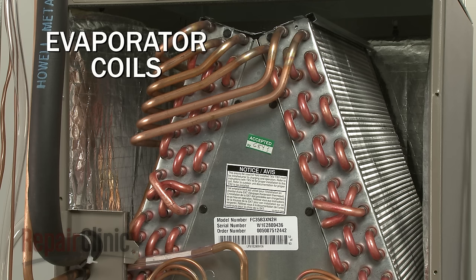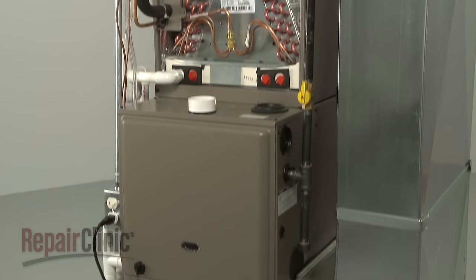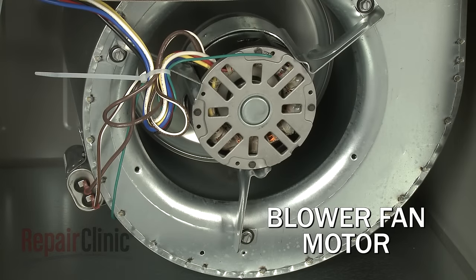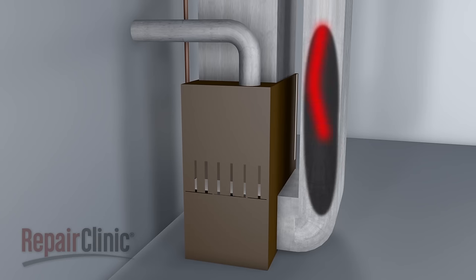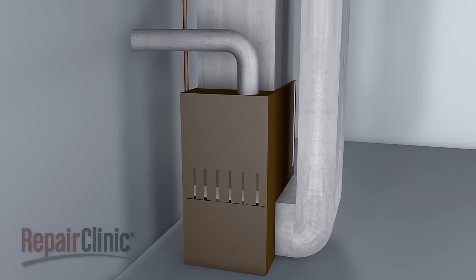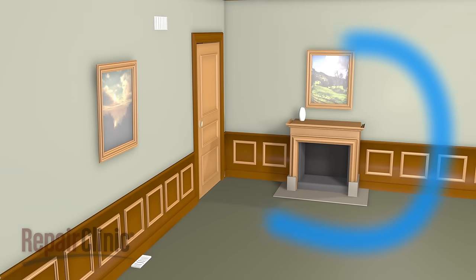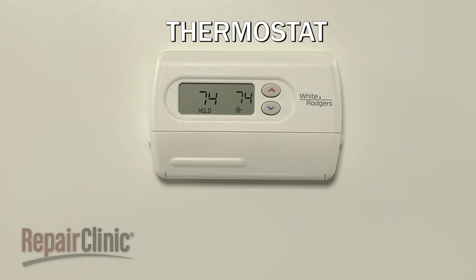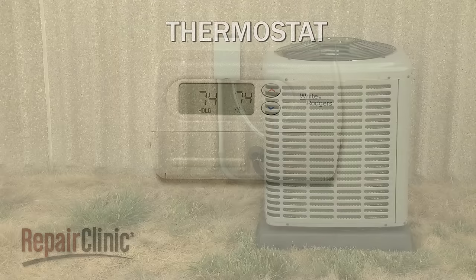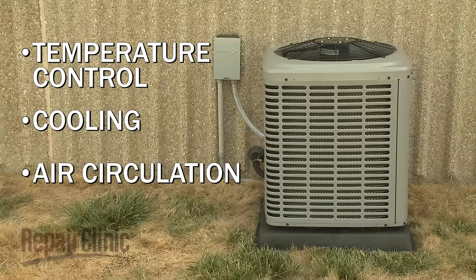The evaporator coils, or cooling coils, are located inside the home and are mounted on top of a furnace or air handler. The furnace or air handler uses a circulation blower fan to draw air through the return vent, blow it past the evaporator coils, and force the air through the home's venting. The room air is then drawn back through the return, and the airflow cycle continues. Once the room air has cooled sufficiently, the wall thermostat signals the circulation blower fan and condensing unit to turn off until the room temperature increases. This process can be broken down into three main factors: temperature control, cooling, and air circulation.